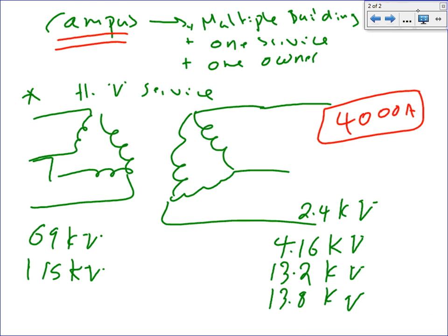If I go to the next slide, guys, this is a high voltage service. What is a high voltage service? More than 600 volt. Can I use a high voltage service of more than 600 volt? Yes, no problem. UVM is using it, if you work with UVM. 3M is using it. Mayo Clinic is using it. These are the types of buildings, guys, that can use a high voltage primary service. They call it primary service. Higher than 600 on the secondary side, okay?